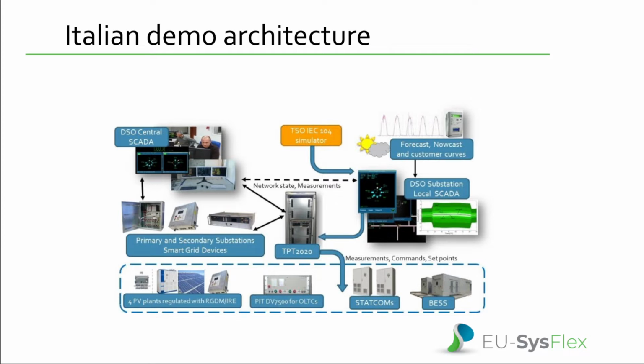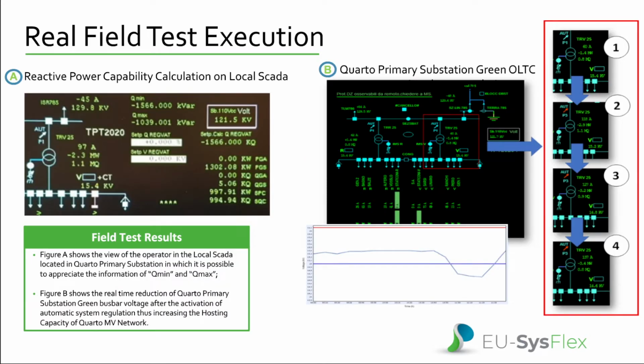and the same local SCADA, thanks to the action of the remote terminal unit located into the primary substation called TPT 2020, and thanks to all the smart grids devices connected to the flexibilities, is able to apply these portions of set point to all the flexibilities you see in the lower part of this slide. Starting from the next slide, you can see what happened in the real field test execution, and Carla Marino will explain to us what happened with them.